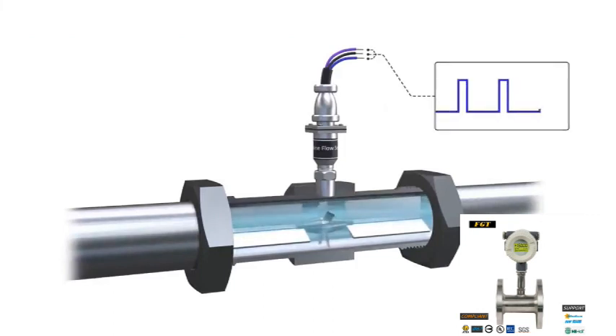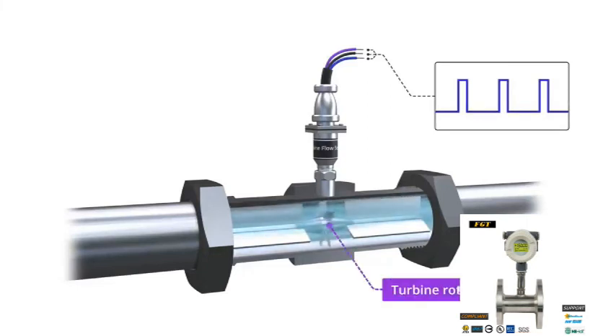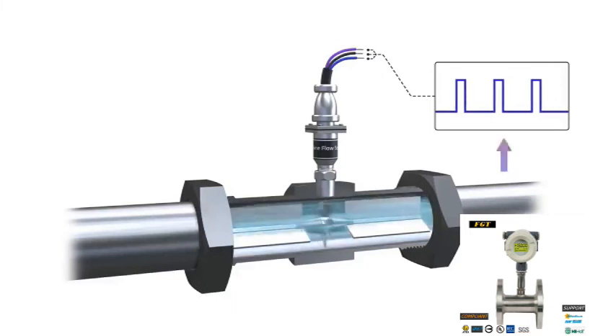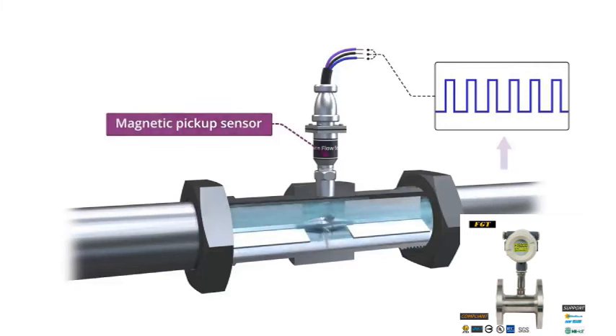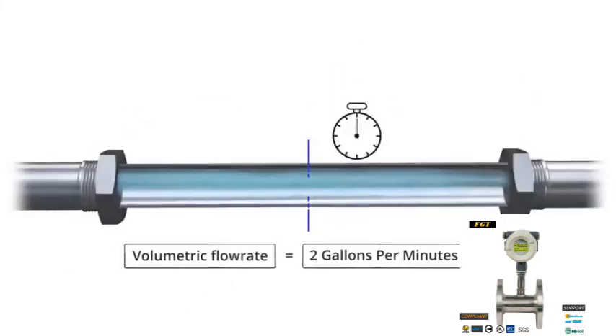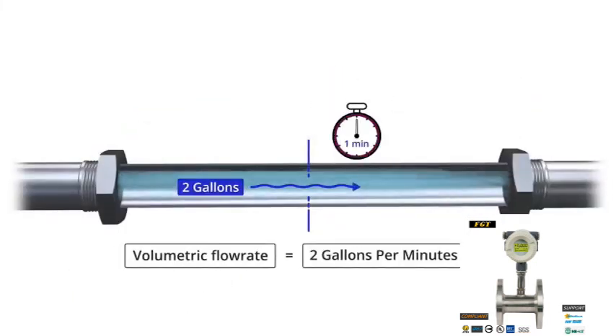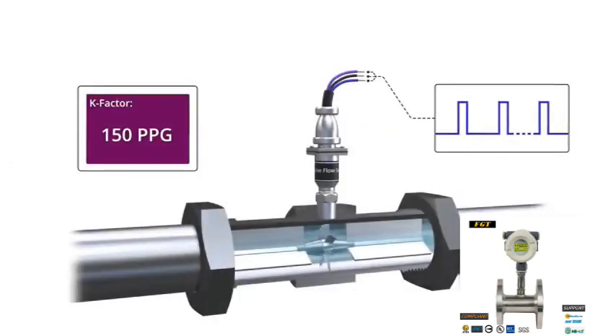Okay, let's review. A turbine flow meter is inserted in a pipe directly in the flow path and has a turbine rotor placed in the path of a flowing stream. The higher the rate of flow, the faster the rotor turns, and the greater number of pulses generated by an electrical pickup. In most applications, a turbine flow meter is used to measure volumetric flow rate. Every turbine flow meter has a unique K-factor stating the number of pulses that will be generated for every unit of product passing through it.